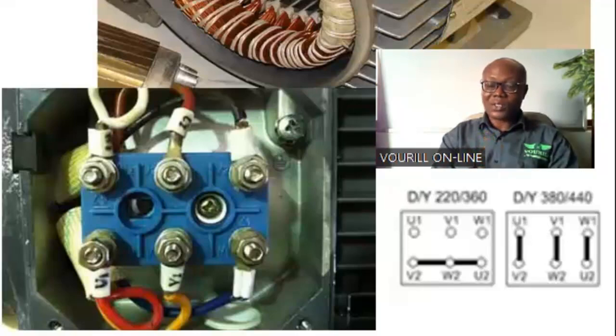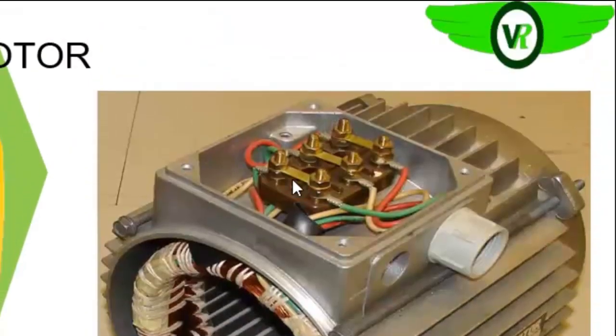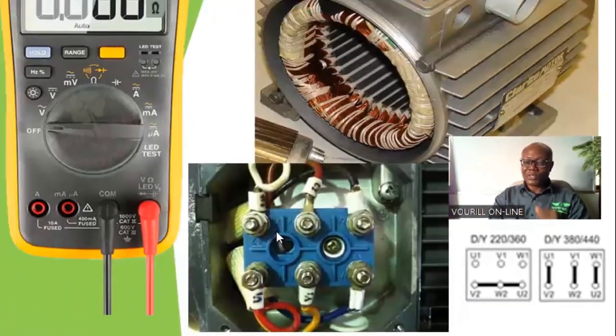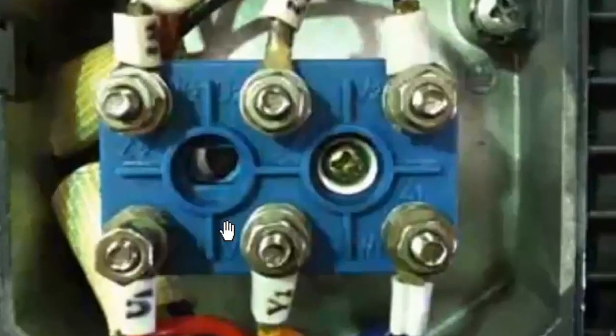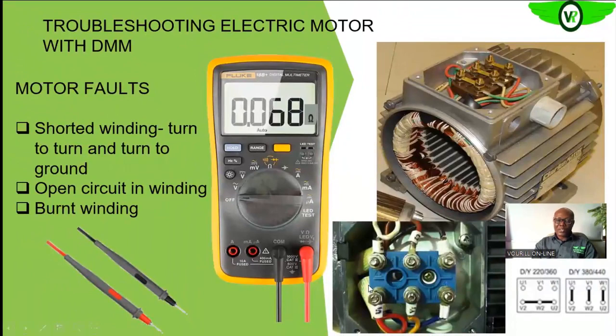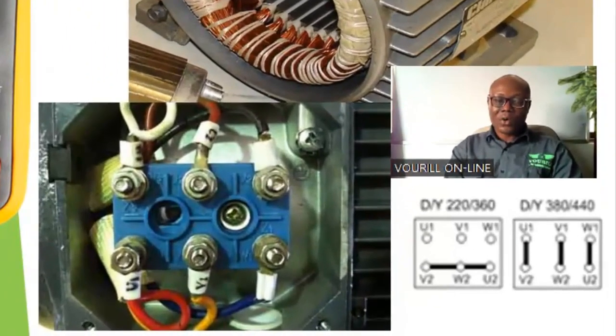So before you carry out your test, all these shunting bars, whether you are delta connected or star connected, you will disconnect them, and then you have something like this. As you can see, this is V2, this is W1, this is U2, and this is U1, this is V1, and this is W2. So now what you want to do is to test each of these windings, whether any of them is shorted within or any of them is shorted to the ground. That is one test that you want to do.